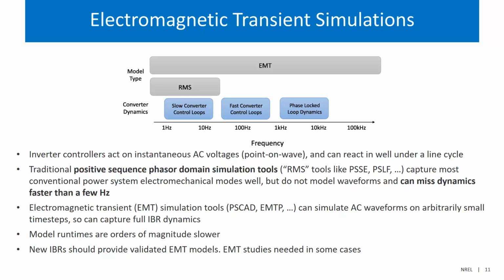And we need to actually use something called electromagnetic transient simulations, or EMT simulations, which means tools like PSCAD or EMTP or others that can actually simulate those AC waveforms and simulate the full details of how the inverters respond to those dynamically in the system.